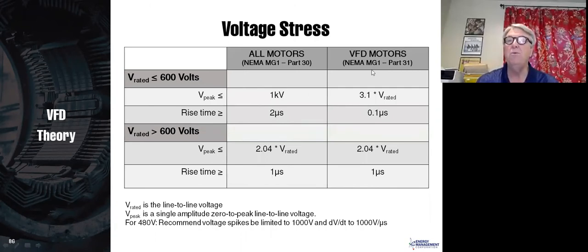A VFD rated motor has insulation that's 3.1 times the rated voltage. I'm just going to call that 1,600 volts, because 1,600 volts is a very common VFD rated insulation. Whenever you have a VFD, always get a VFD rated motor, and this is the chief thing that defines what a VFD rated motor is. That is the premium insulation. It's also able to withstand higher rise times when we have that PWM waveform going on and off.